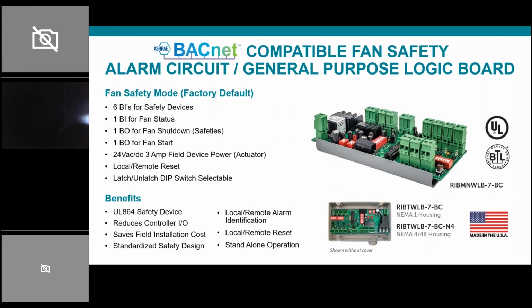So some of the benefits to this board, it's a UL 864 life safety device that does have a standalone function, meaning that once the device has been configured over the network, even if we do lose network connection, it'll still function properly. This can also help reduce controller inputs and outputs, having it BACnet enabled. You can also identify whatever safety goes into alarm either from the board itself or over BACnet, and you can reset the board locally or over the network.